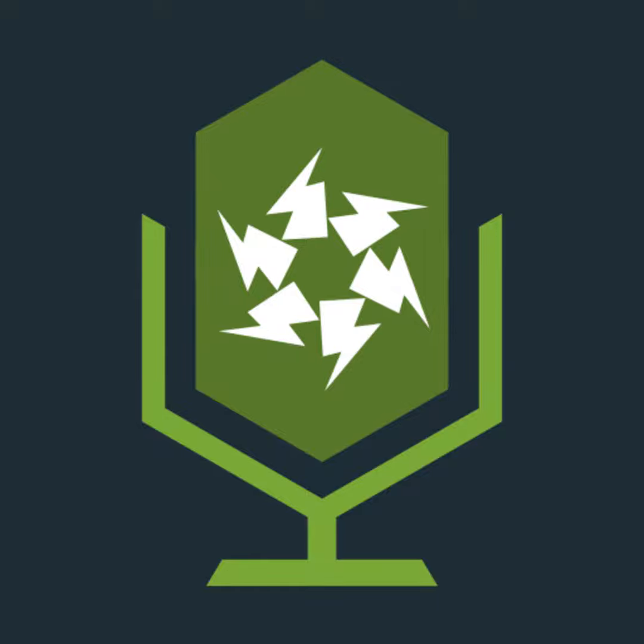When you do a distribution circuit, you don't want to achieve maximum volt drop. You need to make sure that your volt drop is fairly low so that the circuits, maybe even further distribution circuits going onto it, or final circuits, have an allowance of volt drop. Volt drop is total from the origin to the final point of utilization. So a distribution circuit should really just barely touch the volt drop allowance. Similarly with the principles of earth loop impedance and things like that, we don't want to put in a circuit that's going to basically shaft the person who's going to then have to work on the end of that.